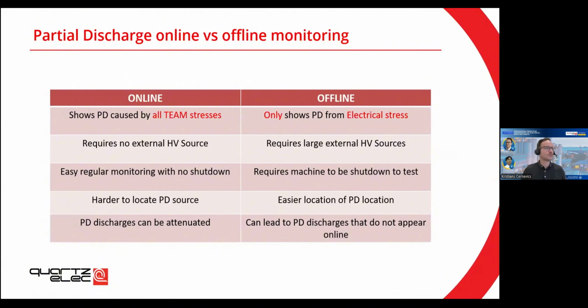And just before I go further, this previous measurement was made online. But like I said, you can do both online and offline measurements. In the next slides, I'm going to introduce a bit more about the types of measurements you can do. The main thing that differs is that online measurements show the PD discharges happening while the machine is operating. So it's going to show you all the PD discharges through all the stresses: temperature, mechanical, ambient.